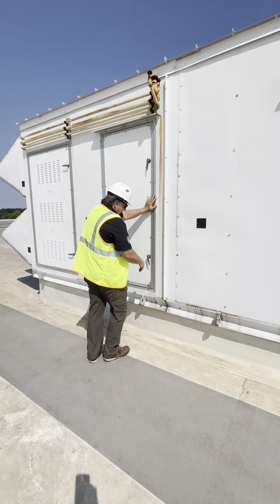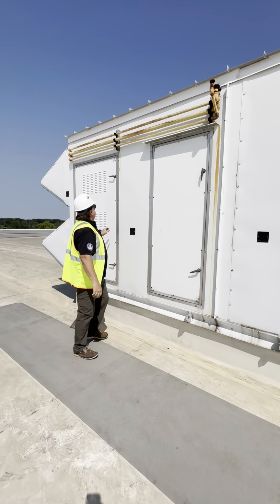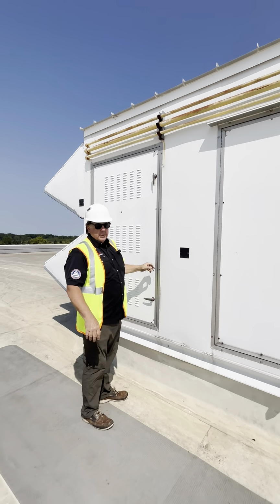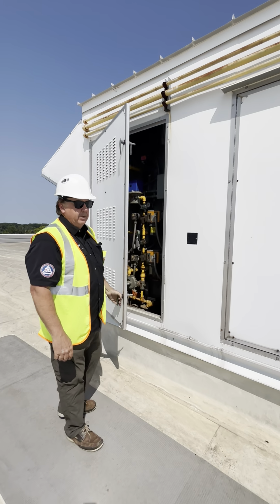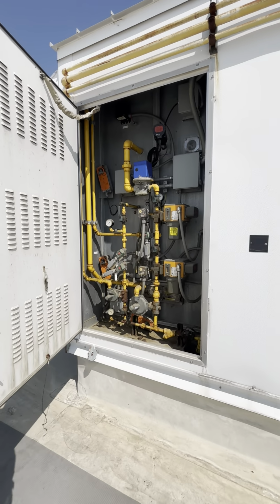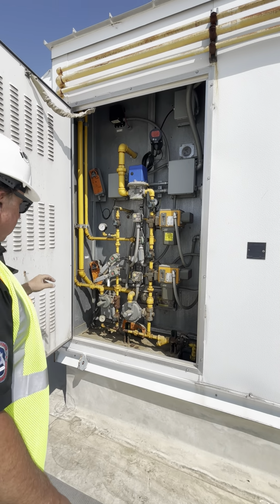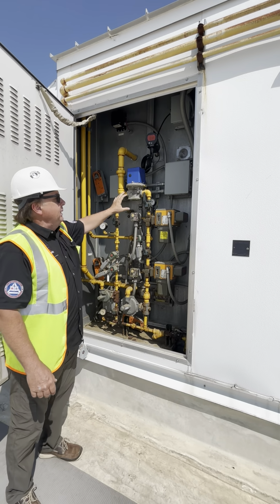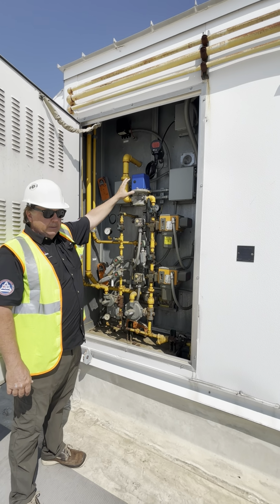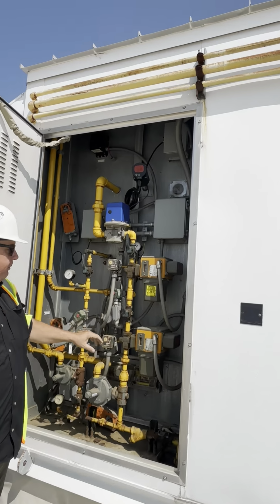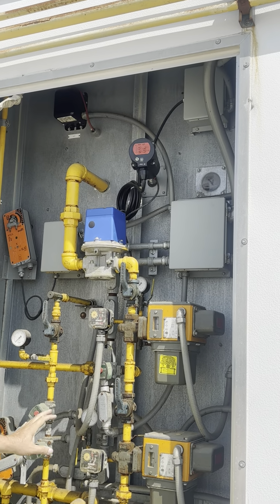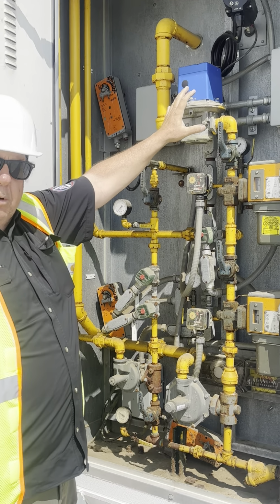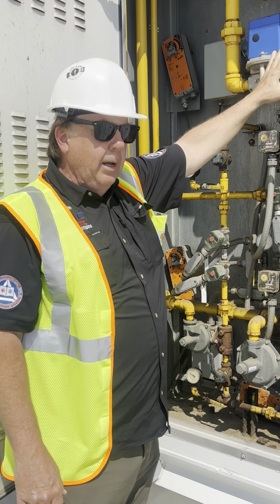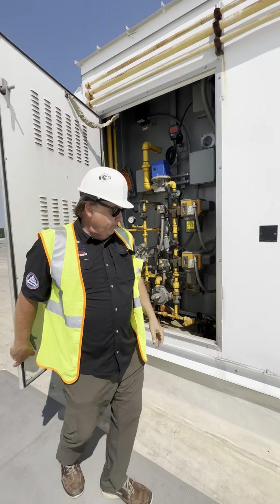And then if we move down to the final section, we can see the control part of the gas furnace, which is a little more substantial than you would look at in most smaller units, but basically it's just a burner, right? So you've got the safeties, you've got the valves, you've got the damper controls, but what you really get when all those things are working is a big roaring fire inside that heats the air.